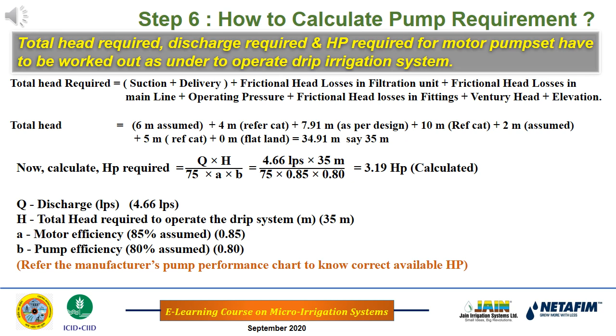Now in this design, Q is 4.66 liters per second, H is 35 meters, 75 is the factor, A is 85%, 0.85, B is 0.80, so it works out to 3.19 HP. It is a calculated HP. To know the manufacturer HP, refer to the manufacturer performance chart. Then you decide the correct HP of the pump.